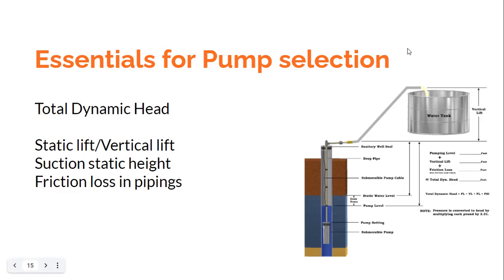You must understand that the submersible pump is submerged in the well, and the depth of the well from the ground is different from the level of the water from the ground. The water level is always higher than the bottom of the well, assuming there is water in the well. We need to take the level of the water in the bore well or open well for calculating the static water level. The static water level is measured from the level of the water in the well up to the surface of the ground — that is the suction static height or suction static head.